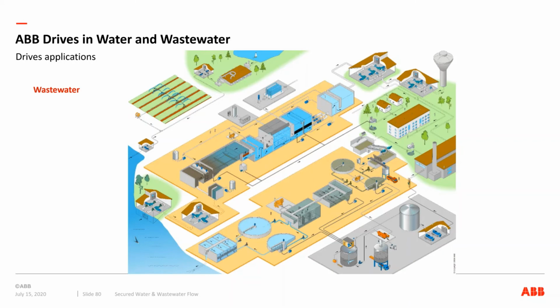Utilizing electronic soft starters, you don't get any big energy savings, but it's less mechanical wear and tear. But putting variable frequency drives on the raw water pumps, on the lift stations, on the clarifiers, on the blowers, on the belt presses, on the RAS pumps, and on the large clarifiers with rakes moving around them. Those rakes are increasing and decreasing speed, and if you put a variable frequency drive on there, it makes it work better, more consistently, because as it builds up debris, it knows there's debris built on it. It can send out an email or a warning to somebody and say, hey, somebody needs to come out here and have a look at that.